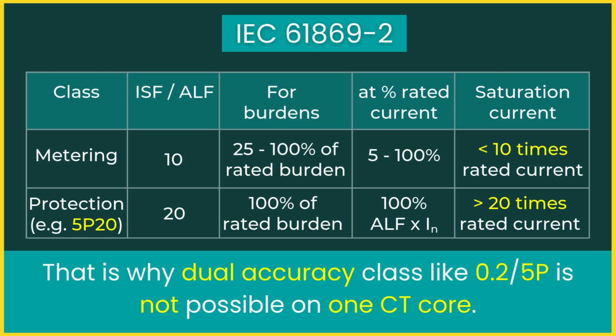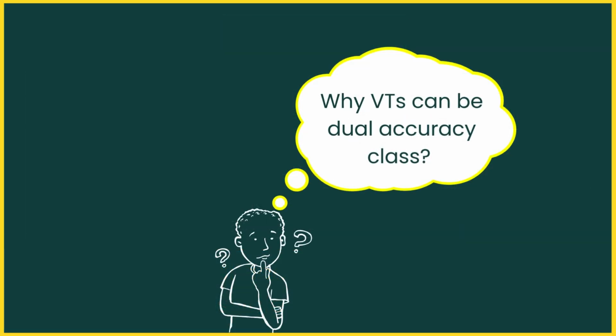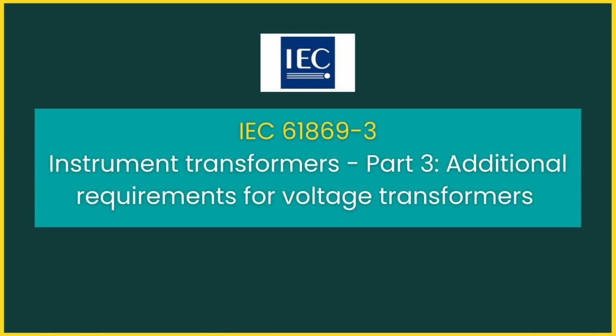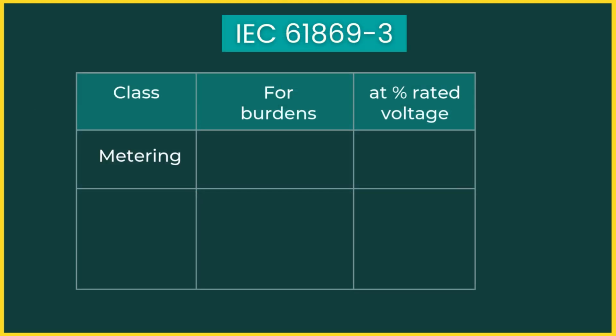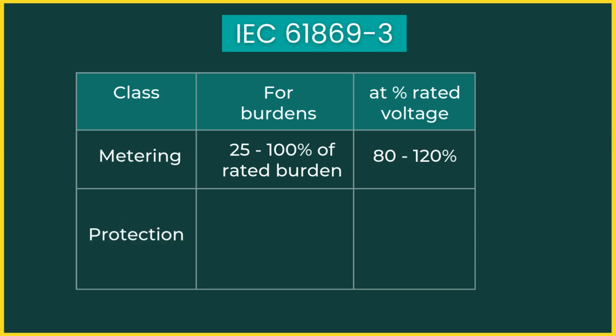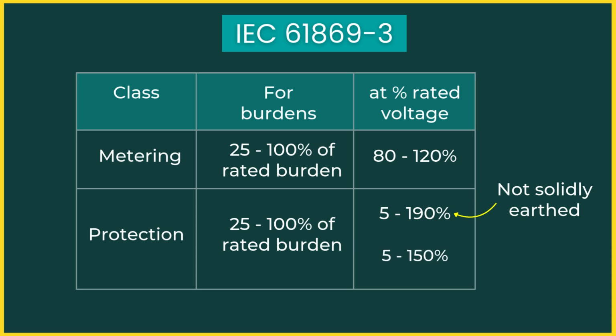Now that CT behavior is clear, let's move to the opposite case, VTs, and understand why VTs can be dual accuracy class. According to IEC 61869 Part 3, a metering class VT must maintain accuracy within limits for 25 to 100% of rated burden, 80 to 120% of rated voltage. And a protection class VT must satisfy accuracy limits for 25 to 100% of rated burden, 5 to 190% of rated voltage for systems where the neutral is not solidly earthed, or 5 to 150% of rated voltage for systems with solidly earthed neutral.